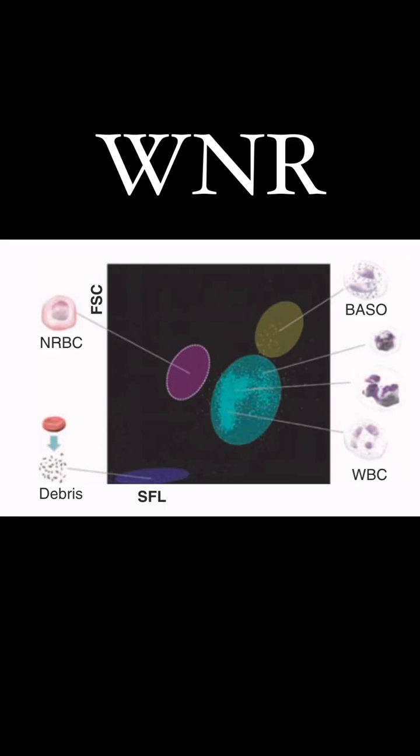Let's look at the image. In these reports, apart from forward scatter and side scatter, there is one more parameter: SFL, which is side fluorescence. This measures the fluorescence intensity. Nucleated RBCs do not have fluorescence, so they appear on the extreme left, whereas WBCs are fluorescent so they appear on the right, and basophils are very fluorescent so they appear on the extreme right. That's how we separate them.